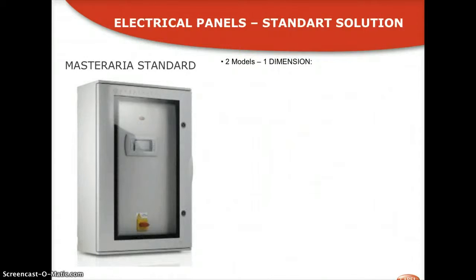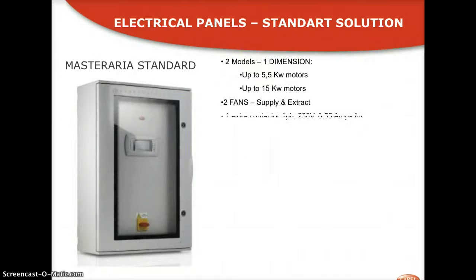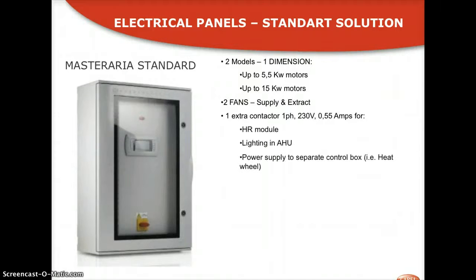The standard comes in two models with one dimension, meaning to say just one box, one size. The two models are one that covers fans up to 5.5 kilowatts and one that covers fans at up to 15 kilowatt motors. These can be supply and extract fans. There is a third additional contactor instead, which is single phase 230 volts, with which you can power supply heat recovery modules, the lights inside your handling units, or anything else like power sockets for laptops and other things.